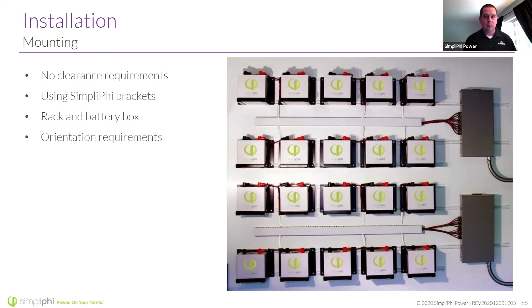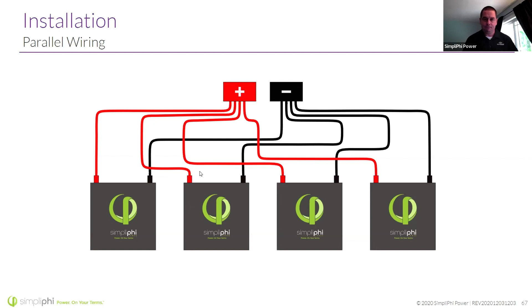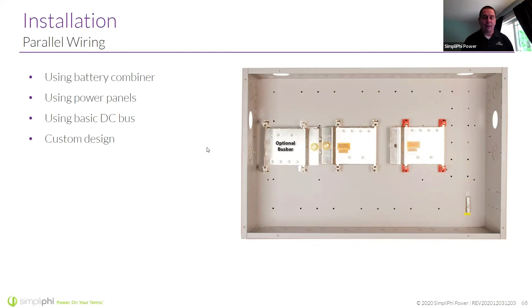Parallel wiring - in this example you can see we've got equal length battery cables. This one has to snake around a little because it has so much battery cable. We want all our batteries wired in parallel, never in series. To do that, you might have to go to a DC combiner, where all your parallel leads land on large DC buses, and then your inverter positive and negative are some nice big fat battery cables going to the inverter.